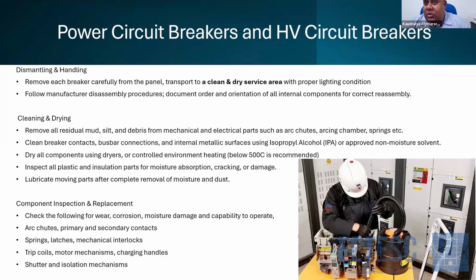You also can use acetone, but not thinner or any other harmful material which melts or deteriorates plastic or ABS surfaces. You have to thoroughly clean them, and you have to dry them. Inspect whether they are very well cleaned.